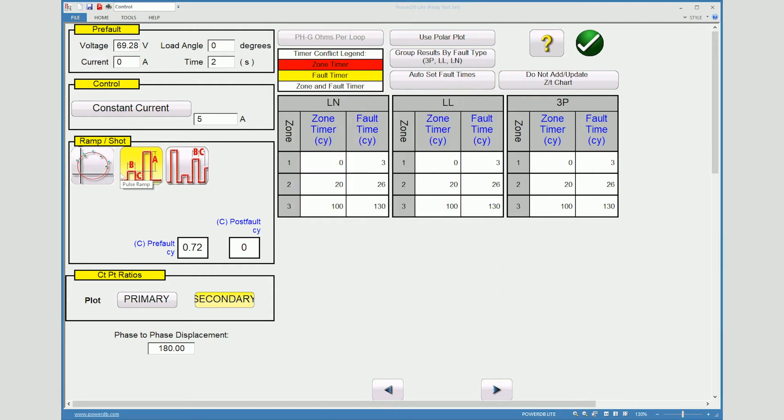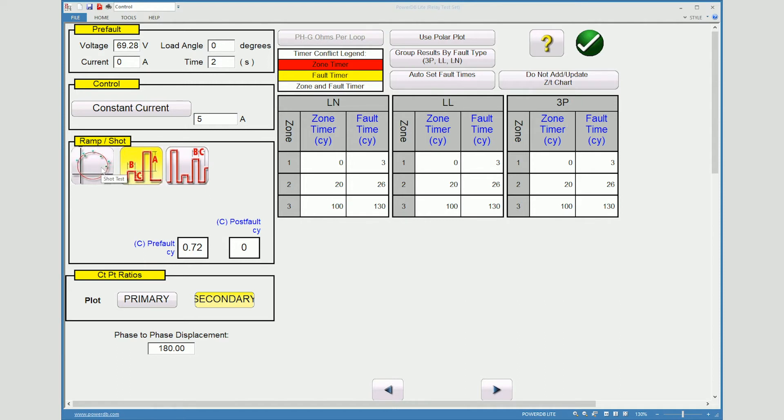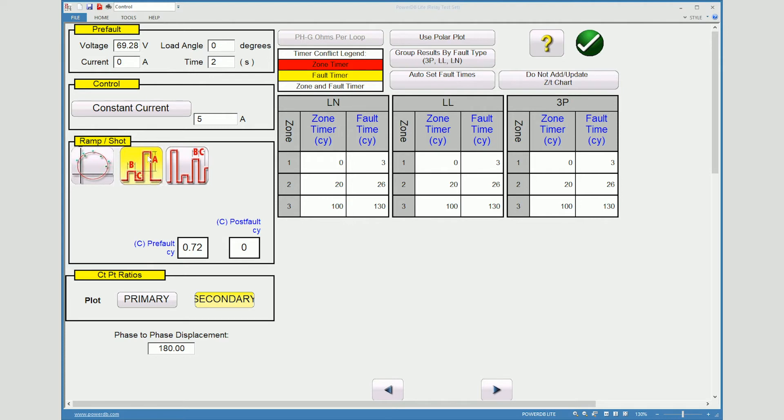Now the different style of test. So each style of test here you can perform a shot test which actually gives you an opportunity to select points in the zone and out of the zone. It's pretty much a go no go test. We can pulse ramp where we would actually take a pulse ramp fashion and move it into the zone from outside of the zone.